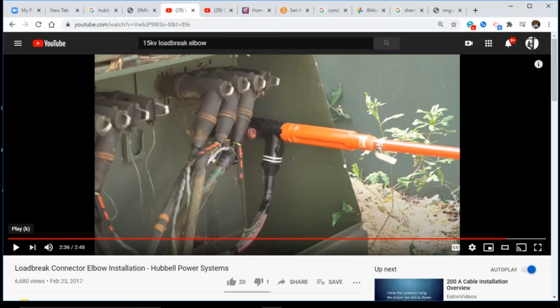All right, you will see some linemen, especially when it's de-energized, that will grab the elbow right here and push it on. If it's de-energized, it's not going to hurt you, but when you do that, you're putting stresses onto the conductor right at the tip, and it's going to degrade the tip. You've got to use a stick. A stick pushes all the force from the back of the elbow on and off of the insert that you're putting on. So even de-energized, you've got to use a stick to take an elbow on or off any kind of insert bushing.